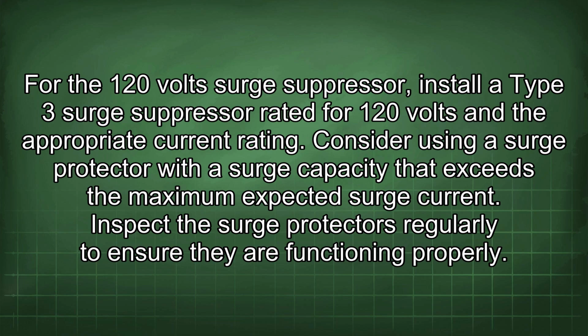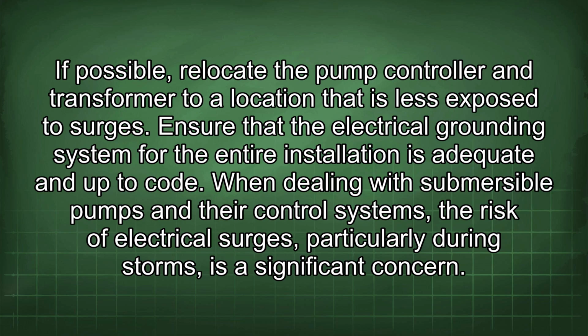Inspect the surge protectors regularly to ensure they are functioning properly. If possible, relocate the pump controller and transformer to a location that is less exposed to surges. Ensure that the electrical grounding system for the entire installation is adequate and up to code.